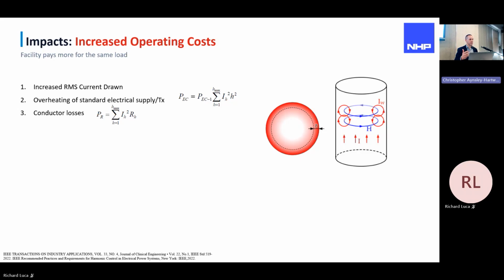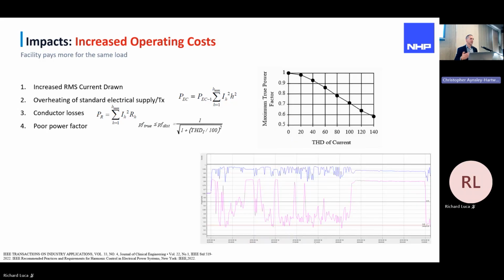It's quite well known in bus bars and cabling. That cross section in red, abbreviated by delta, shows you the skin depth of a conductor. So with increasing harmonic distortion, that skin depth reduces. So a lot of the current is forced to the outer edge of that conductor. So again, there's increased operating costs in the form of losses.